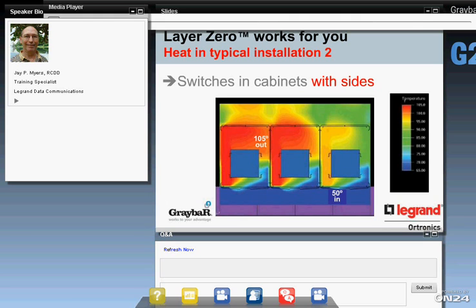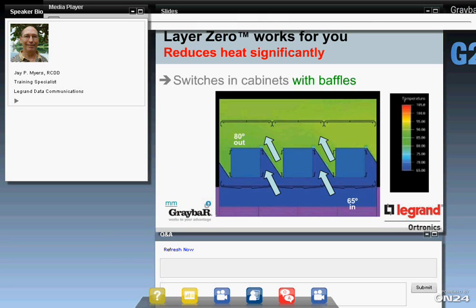So instead of doing that, why don't we just do a little bit of engineering here and install some diagonal baffles from the front corner of one switch to the back corner of the next switch down. So this guides the cool air into the equipment from the cold aisle, and the hot exhaust air is exhausted out into the hot aisle, but it's blocked from circling back around and diluting the cool air going into the intake. So this allows us to raise our ambient temperature back up, saves on electricity, but still keeps our equipment at the temperature that we want.